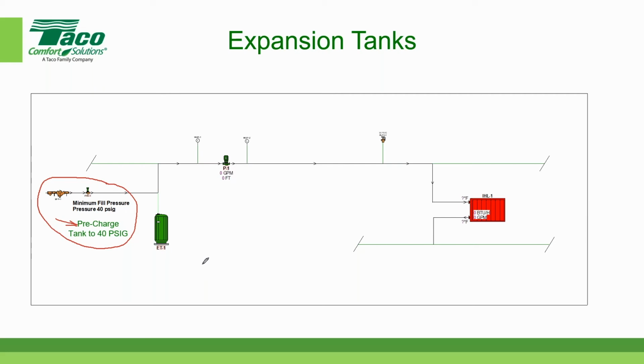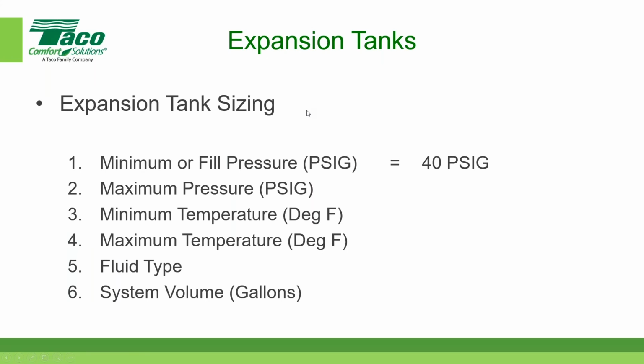So we've just calculated the pre-charge pressure. We've gotten the tank from the factory, and then we add compressed air through the Schrader valve to increase the pre-charge pressure to 40 PSIG before we connect it to the piping system. Extremely important concept. Okay. Now we've determined the minimum pressure or fill pressure. Let's go on and figure out the next thing, and that is the maximum pressure.